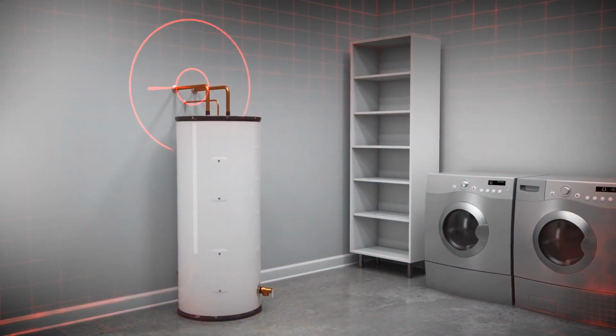The key to maximizing your long-term savings is to choose the right-sized heat pump for your home. This involves a careful assessment of your home's size, insulation, and other factors. Consulting with a professional HVAC technician can help ensure that you get a system that meets your specific needs without being oversized. With an air-to-water heat pump, also called hydronic heat pump, a buffer tank is used, which is sized so the heat pump runs 15 to 30 minutes to get back to its set point.